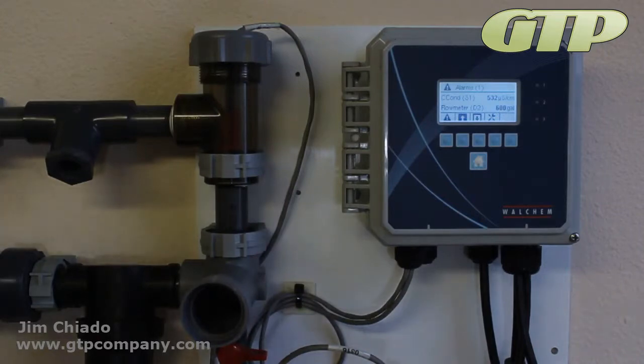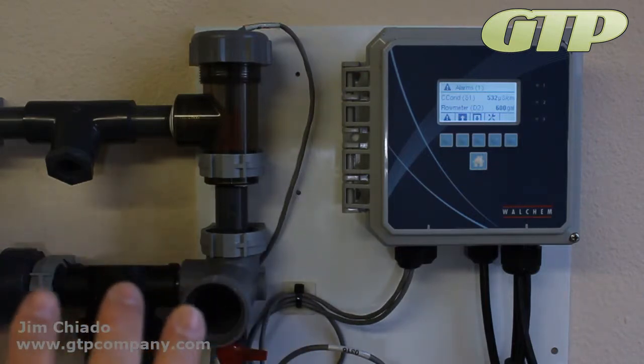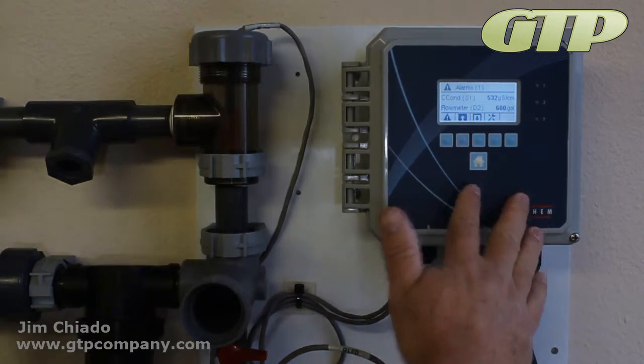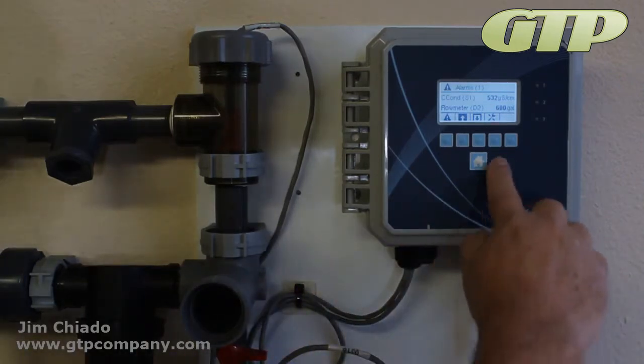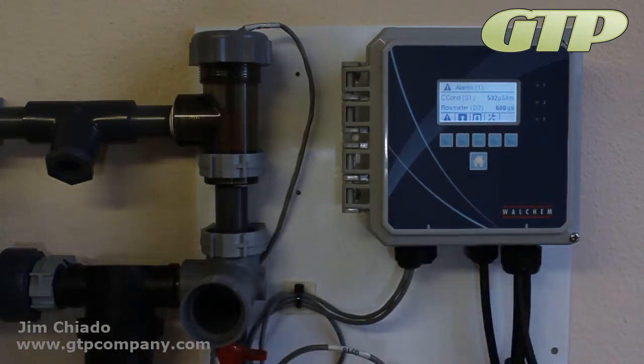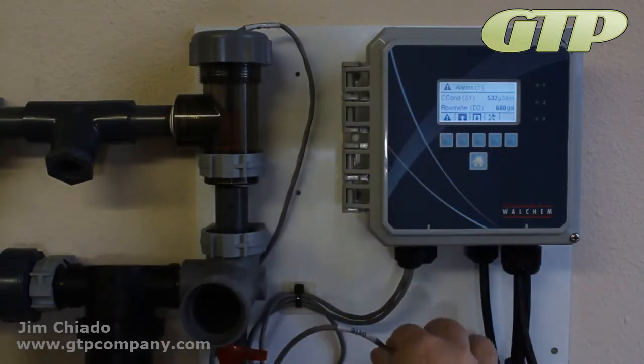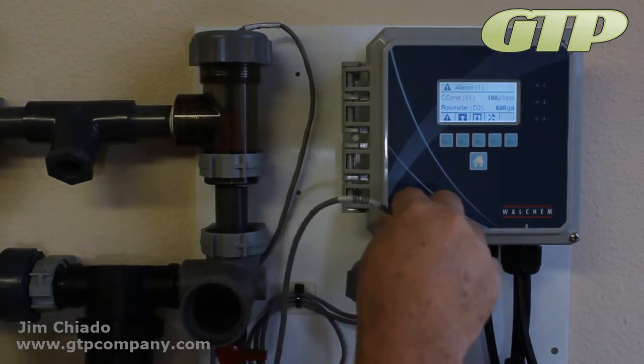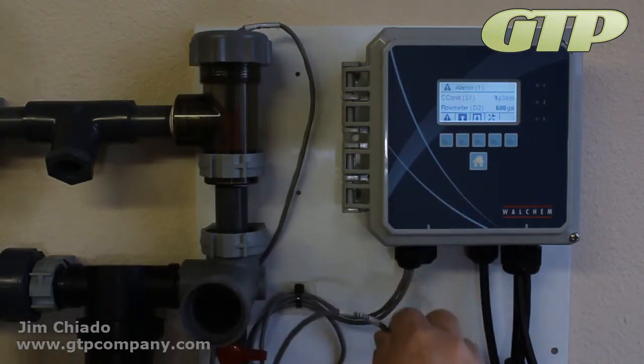Calibration of the sensors, or the temperature portion of that sensor, does seem to prevent a little bit of problems. A lot of people have trouble with it, or they're not having it wired properly. Want to make sure firstly and foremost it is wired properly. Go by the label that we have in there, and see the wiring portion of our video training. And then if it's reading properly, you'll see right now it's out of water, so it's going to drop to 1. It's in liquid, it's going to come back up.